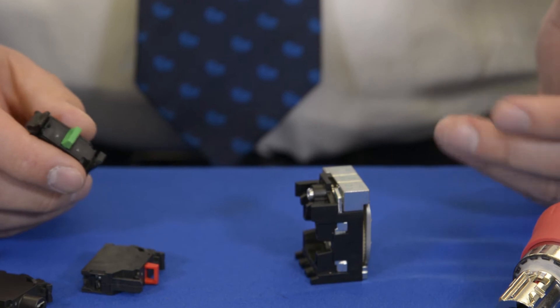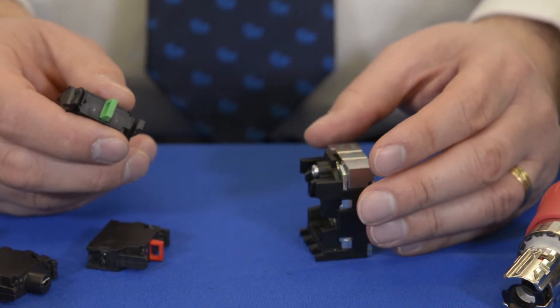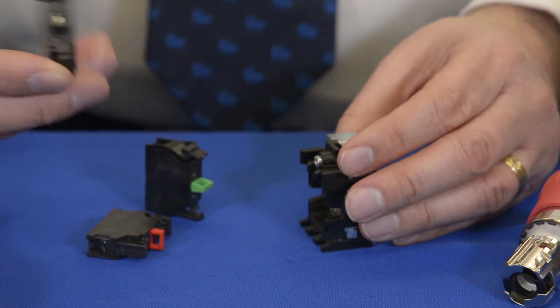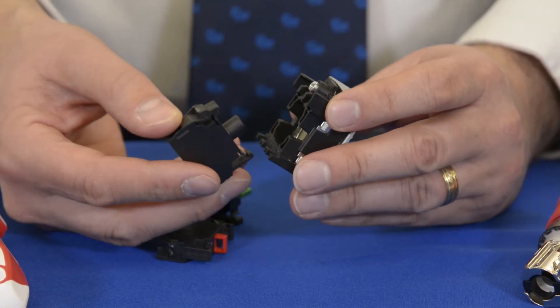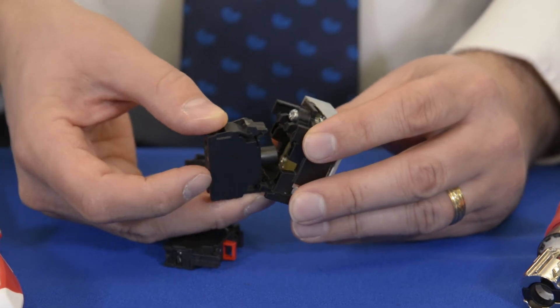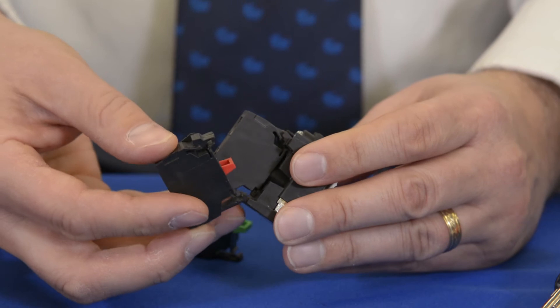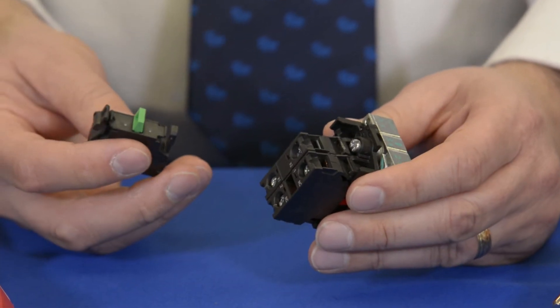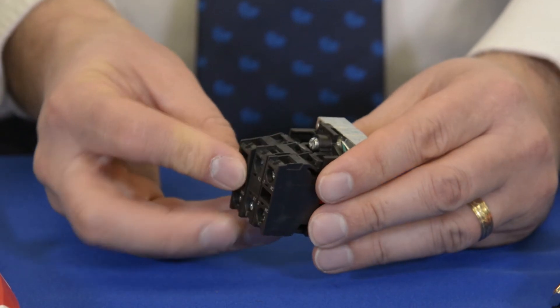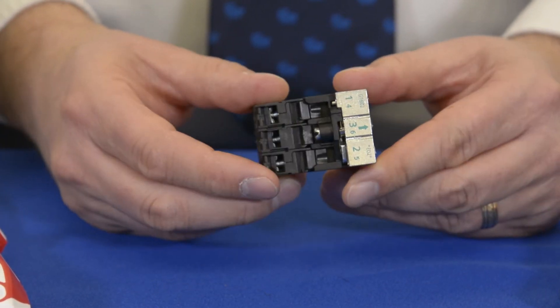Now, if I wanted to add contact blocks to this latch mechanism, it's very easy to apply that. I typically will put the LED, which is always going to go in the center position on first. Insert the small end in the bottom and click in the top end. Put this normally closed contact in next and then this normally open contact block finally. And I'd have two contact blocks and an LED module assembled here.